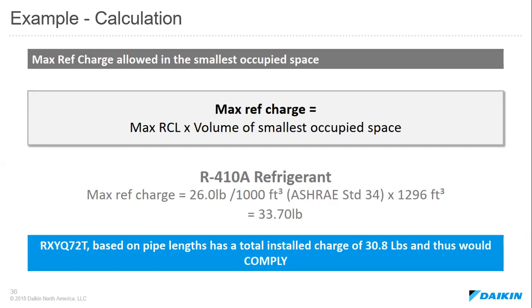And so our maximum refrigerant charge that we could actually put in that space, we can calculate by utilizing the following equation, which is our max refrigerant charge equal to the maximum refrigerant concentration limit, which I mentioned earlier, for R410A refrigerant, is 26 pounds per 1,000 cubic feet. And then that multiplied by the volume of the smallest occupied space, which was 1,296 cubic feet, means that we could have applied up to 33.7 pounds of refrigerant. In actuality, we only have 30.8 pounds of refrigerant being exposed to that space. So in this simple example, our system actually can be utilized in that space and does comply.